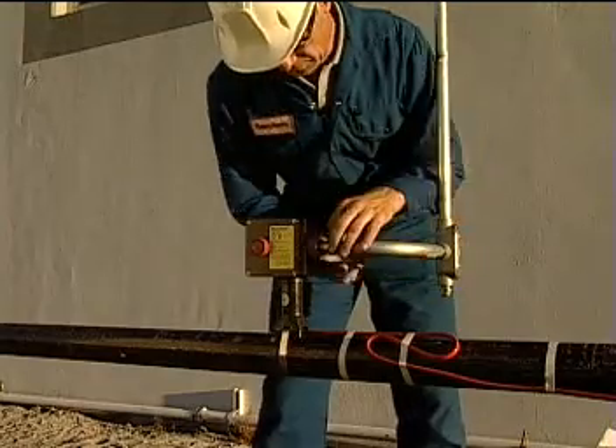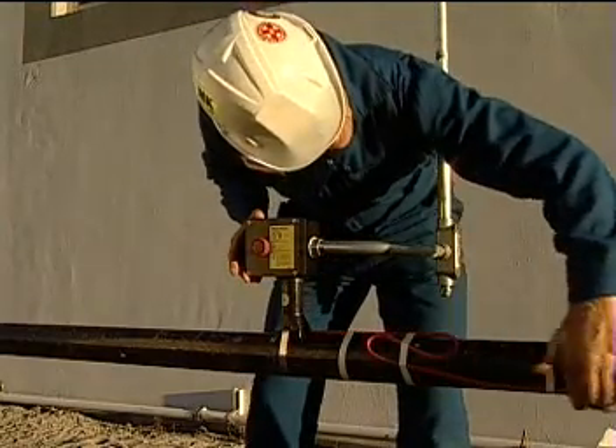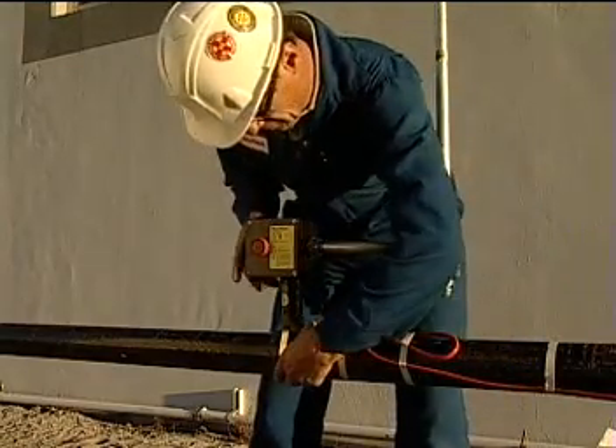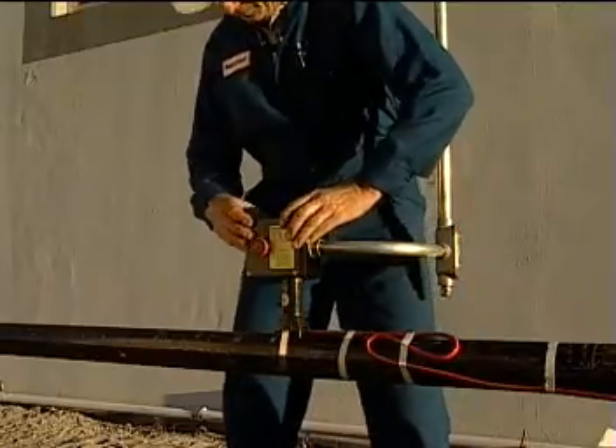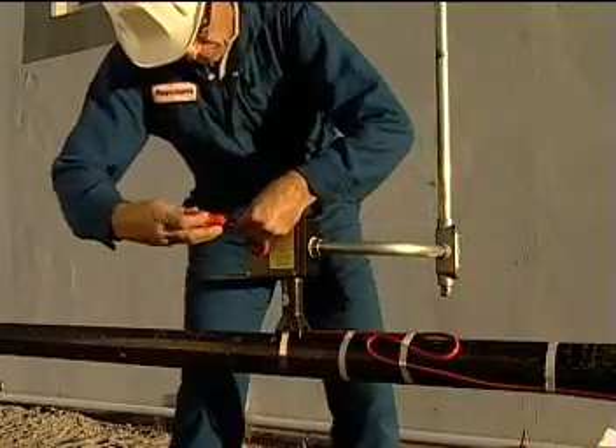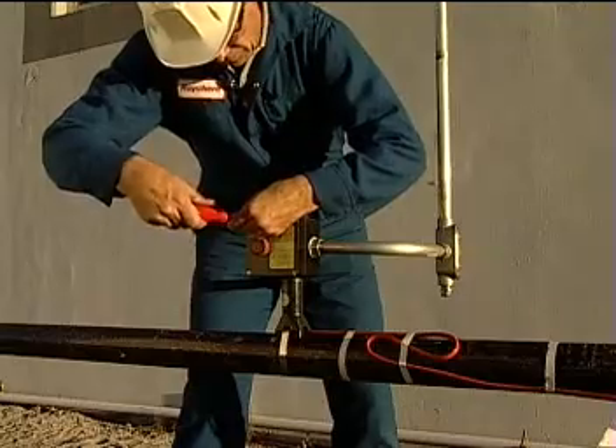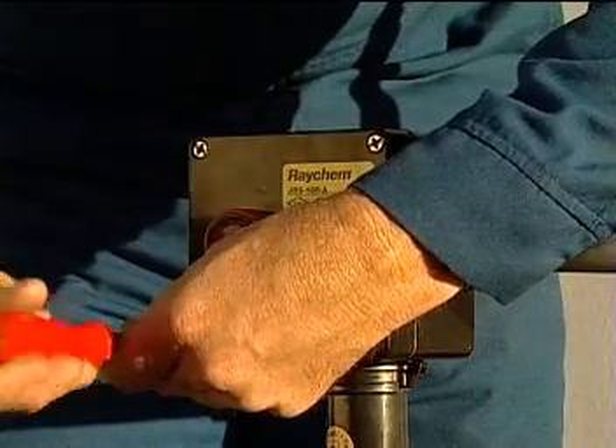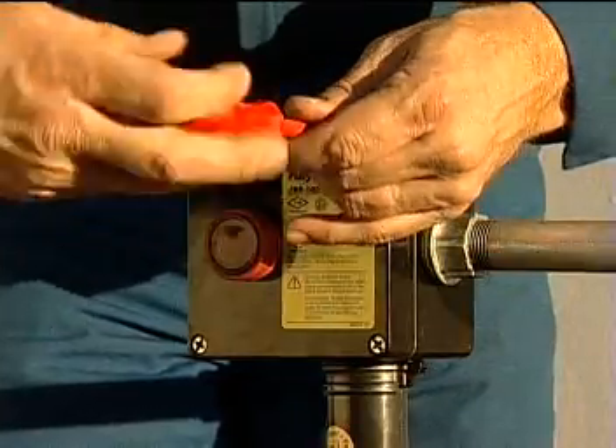Inspect all the connections to make sure that the components are mounted securely to the pipe, that the junction box is securely tightened to the stand, and that it's not been damaged. If you find a damaged cable, don't try to repair it. Instead, remove the entire damaged section and splice in a new length using a Raychem splice kit.